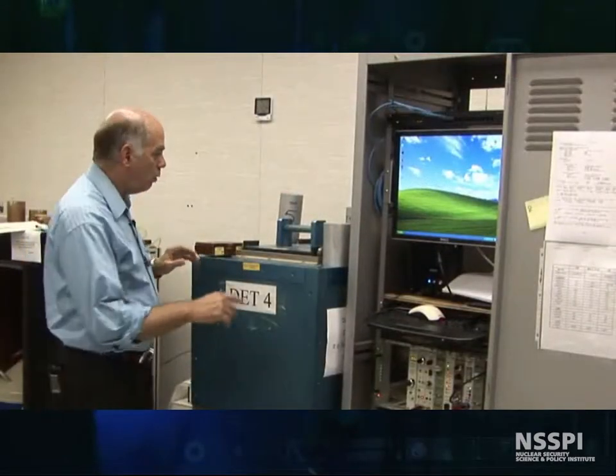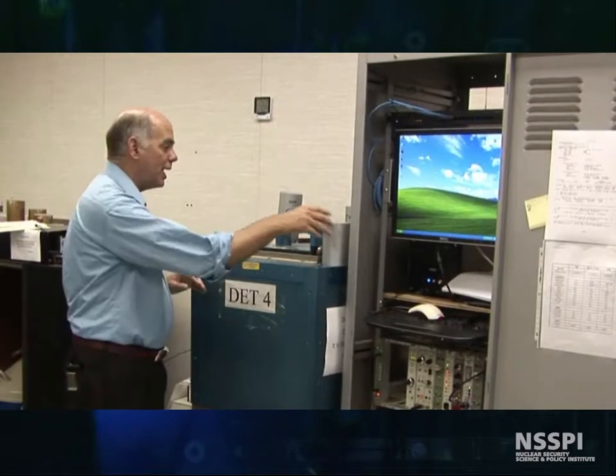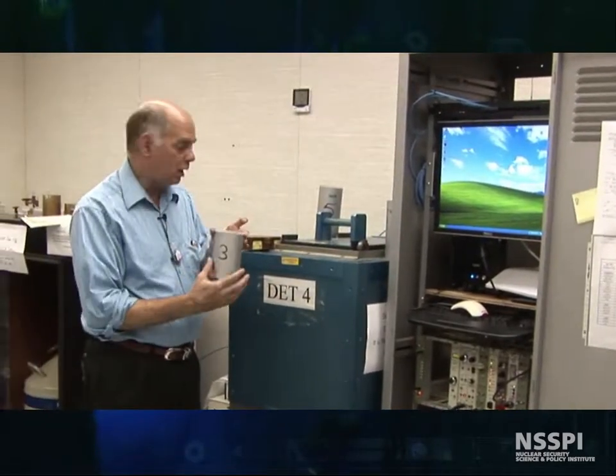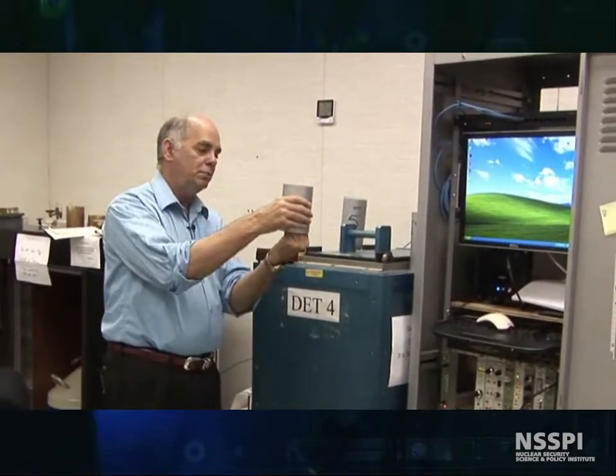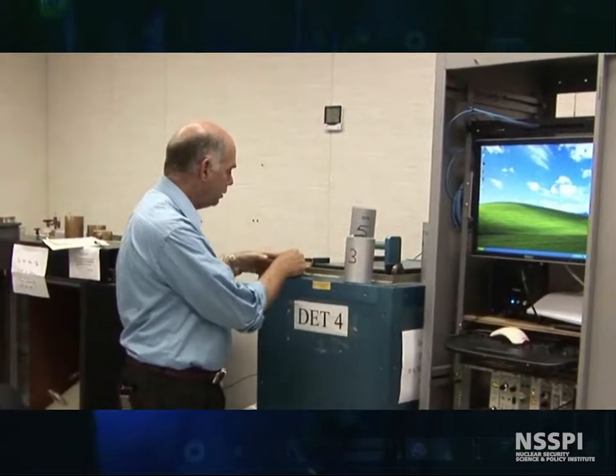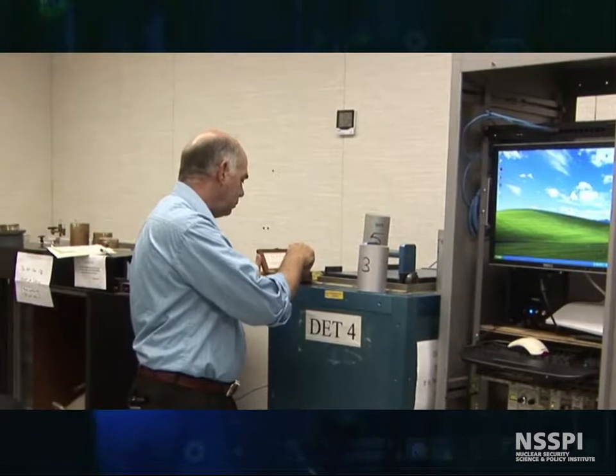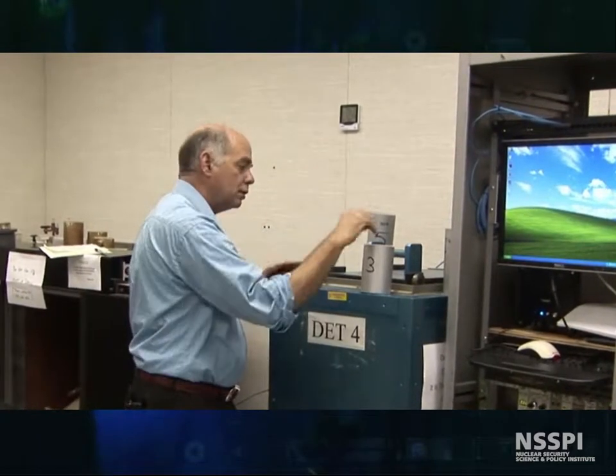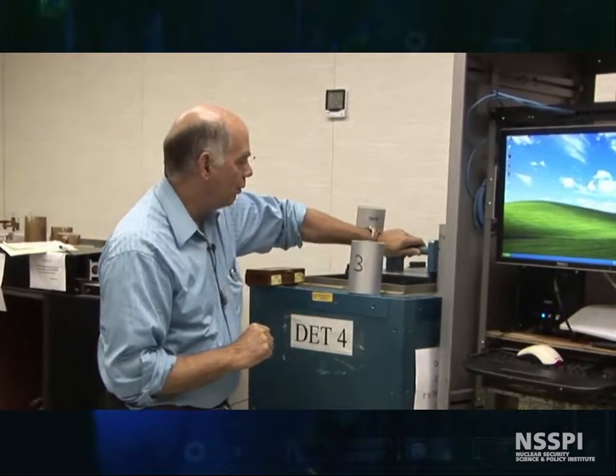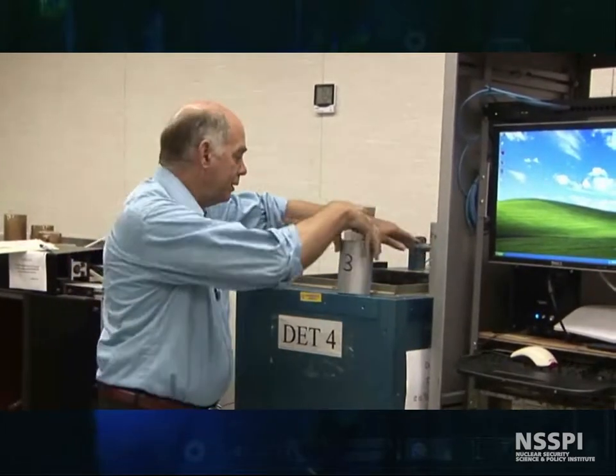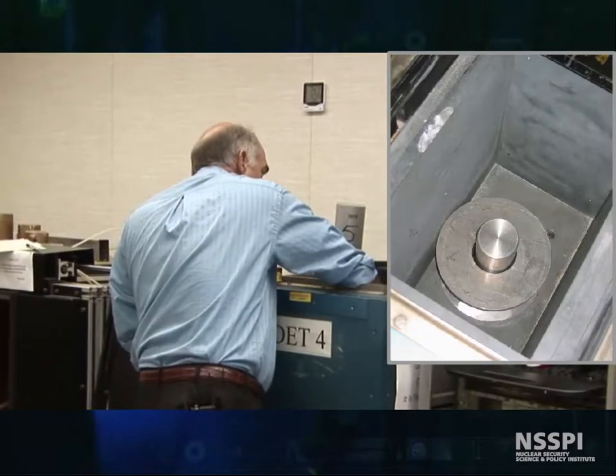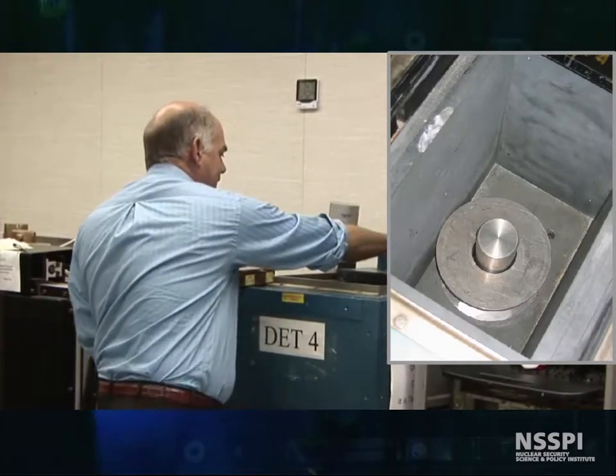What we do in order to fix the geometry, we have stands — that's what we call them. We put these over the detector, and then we can add our cobalt check source like that, so we have a fixed geometry. I roll back the piece of lead, and the whole thing goes inside. And we're ready to go collect a spectrum.